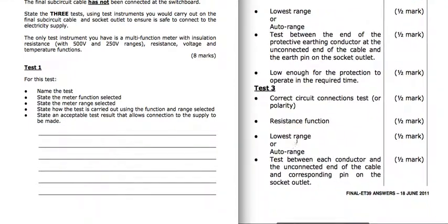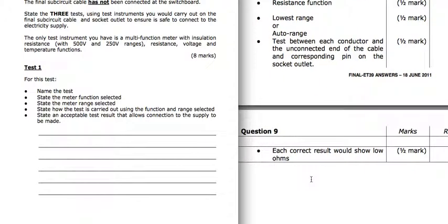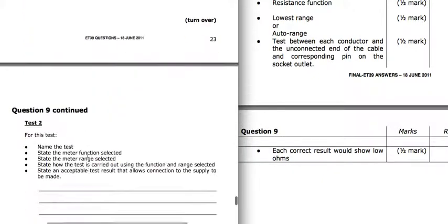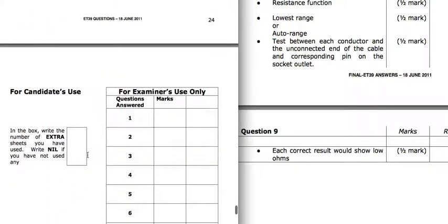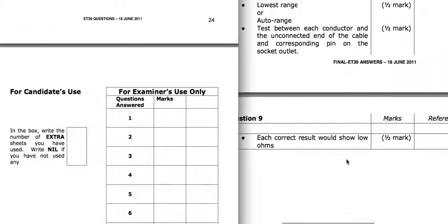Test 3, we're looking at the circuit connections, making sure they're correct. Again, it's a low resistance range, and we're going to go between each conductor at the unconnected end of the cable and the corresponding pin on the socket outlet. So there's a spelling mistake there. So we're just making sure that they're connected to the right end of the cable. And each correct result should show low ohms because it's going to be a continuous cable from one end to the other. So that's going to be our 3 tests, and that finishes that exam.